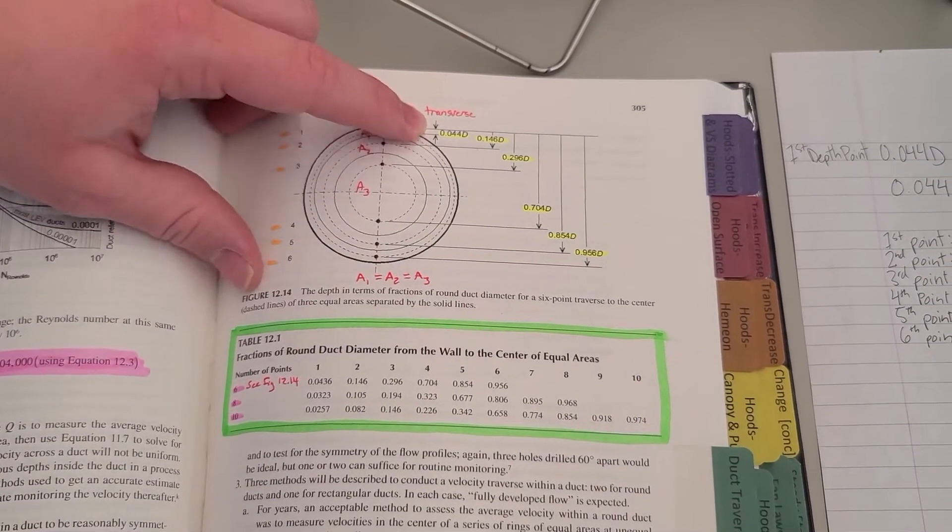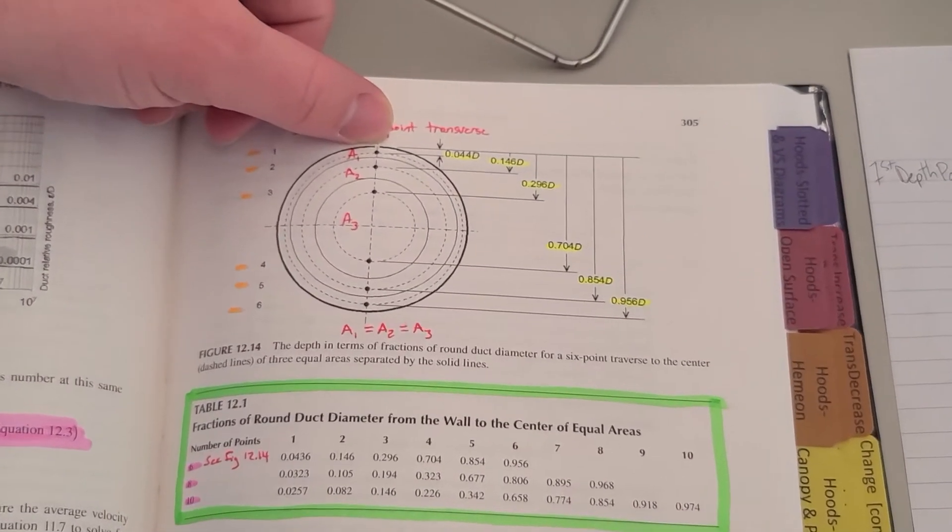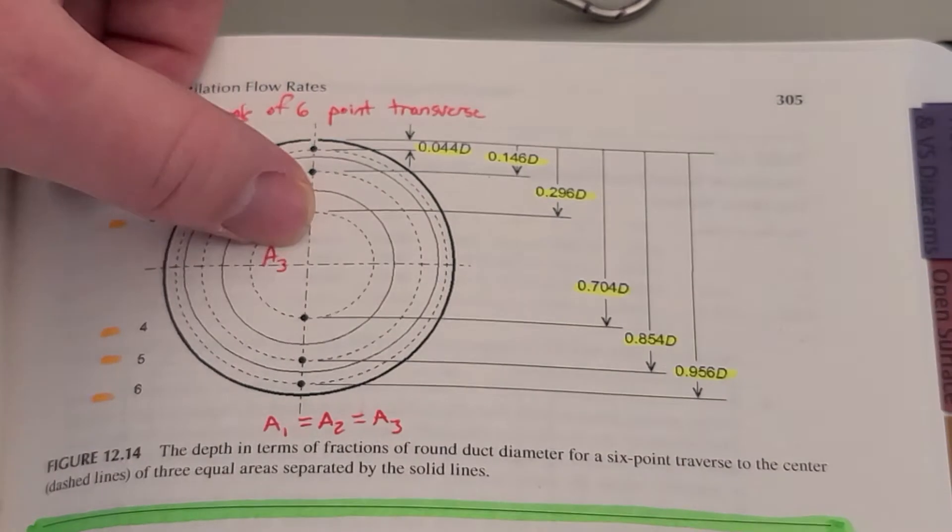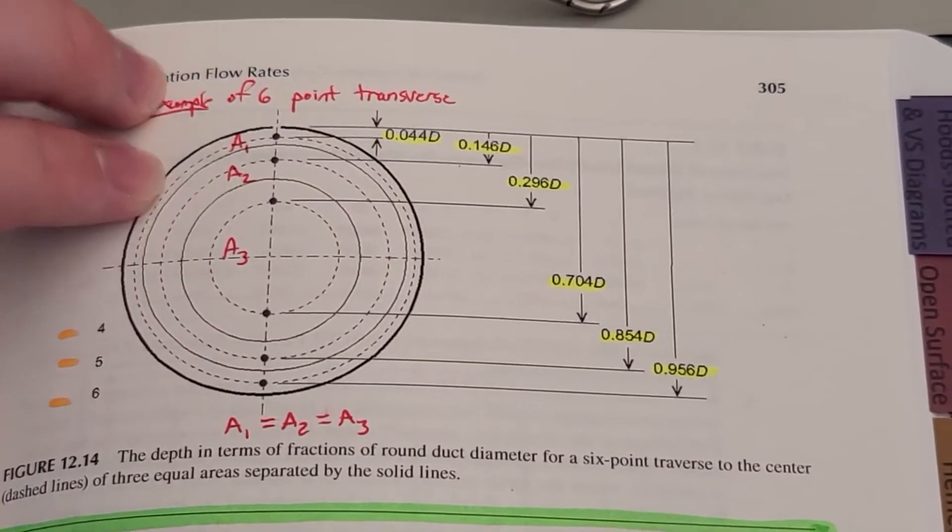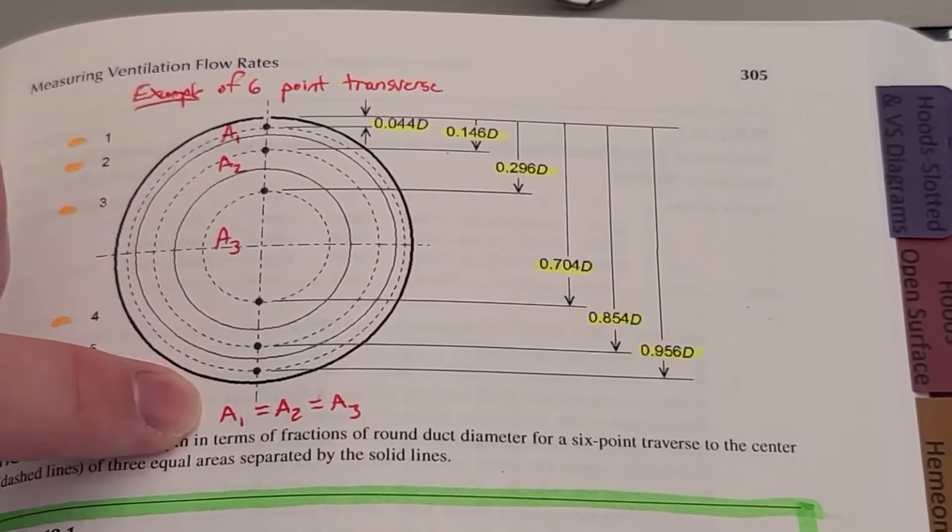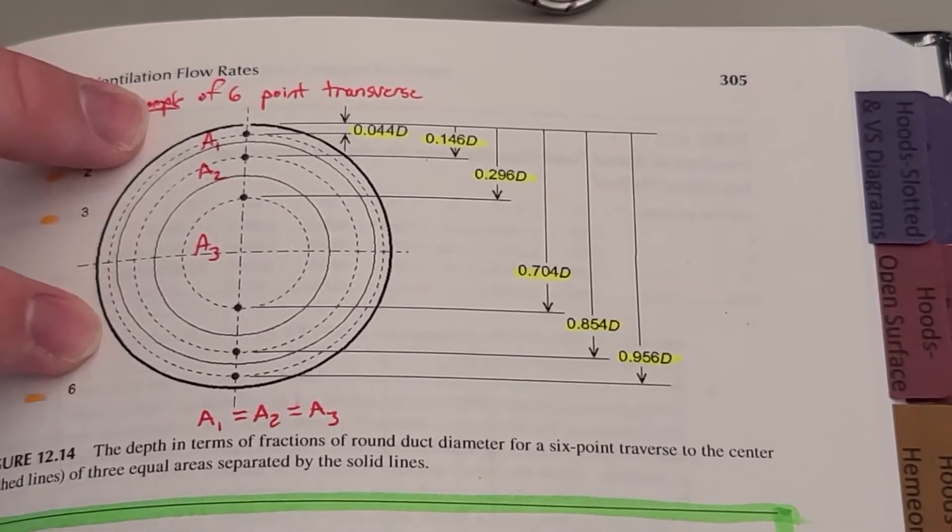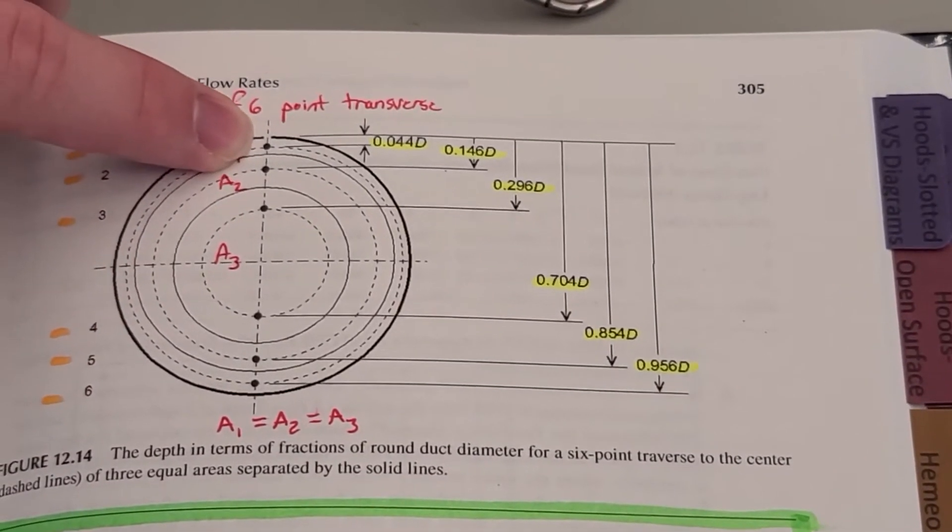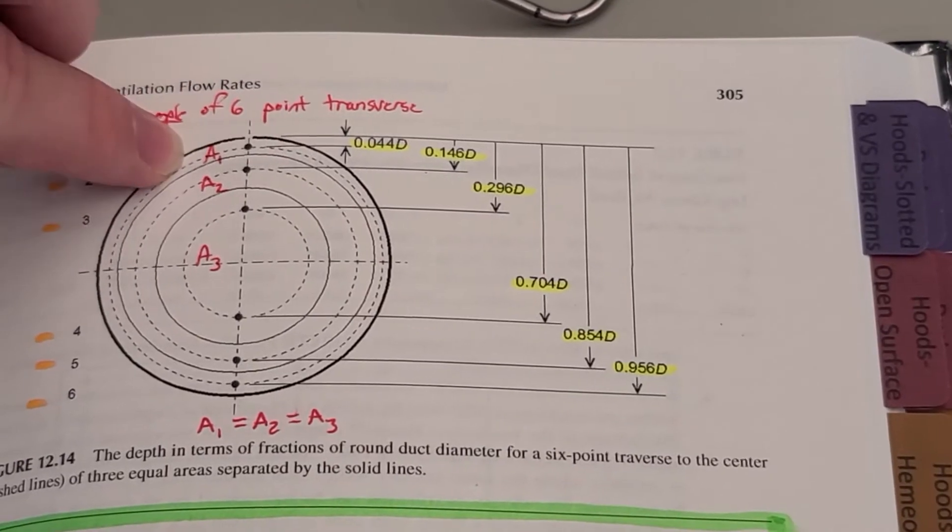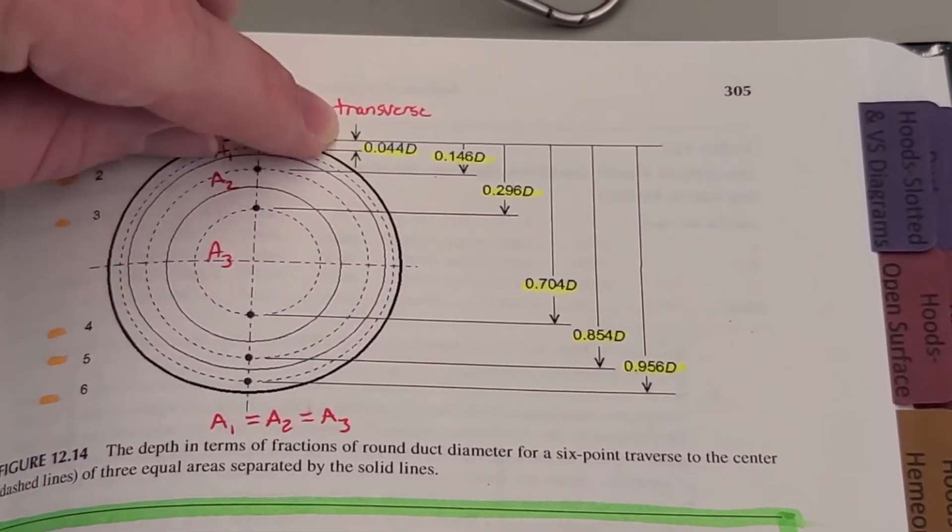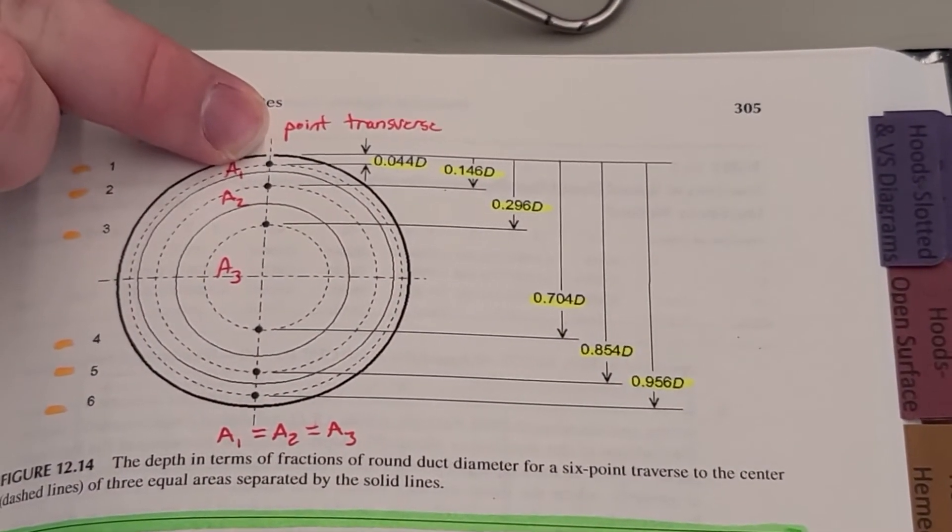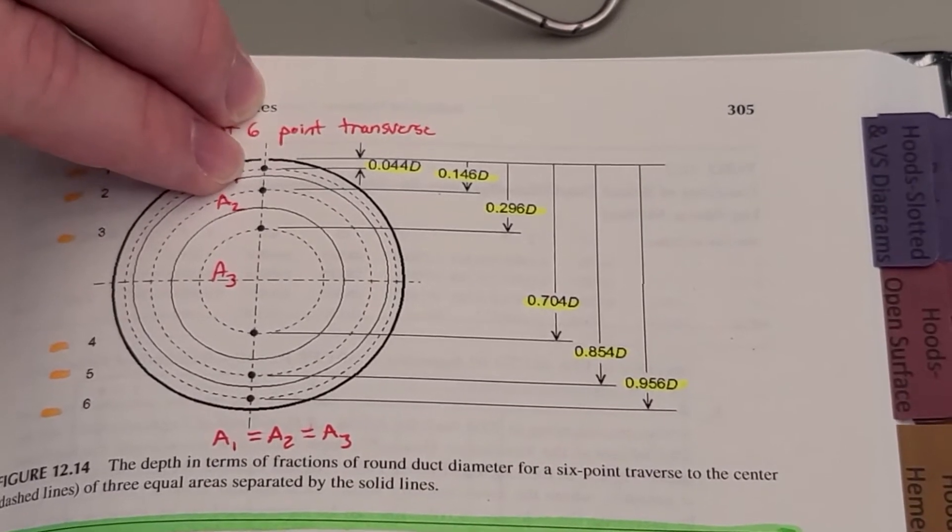The reason that these points vary—if you see, the depths are not equally distributed across the whole duct—is because the cross-sectional area of a circle is not even throughout. Here for the first point, since it is a small ring encompassing a large circumference, it covers a much larger cross-sectional area, so its depth needs to be much more shallow.